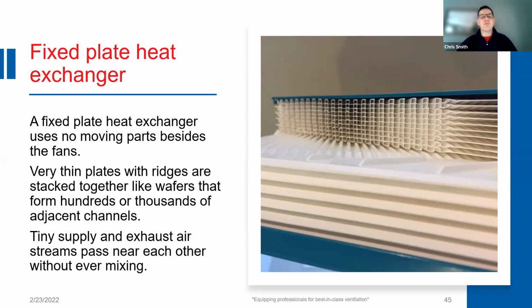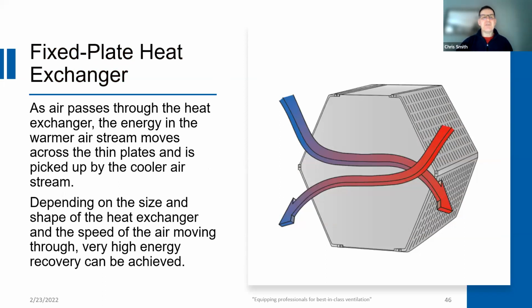These are very thin plates. They have ridges stacked together, forming a wafer-like structure. This creates hundreds or even thousands of adjacent channels. And these tiny supply and exhaust air channels are located adjacent to each other. Exhaust and supply air can pass by each other without ever mixing. As air passes through the heat exchanger, the energy in the warmer airstream moves across the thin plates, does that via conduction, and it's picked up by the cooler airstream. And depending on the size and shape of the heat exchanger and the speed of the air moving through it, you can get really, really high energy recovery.